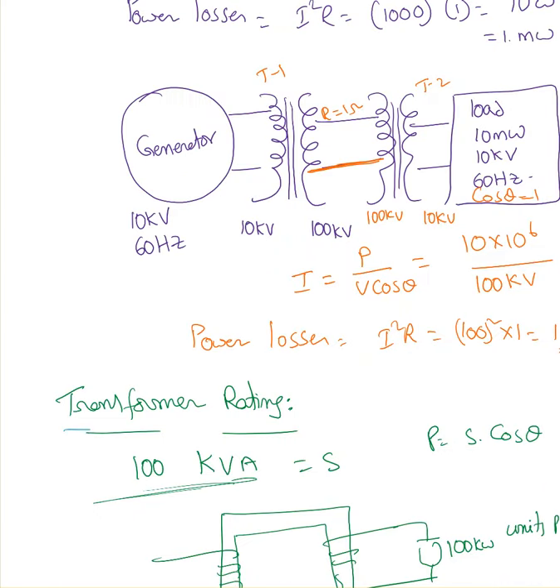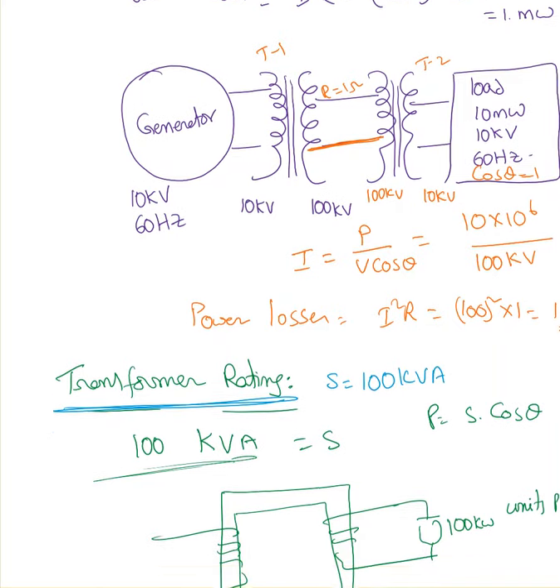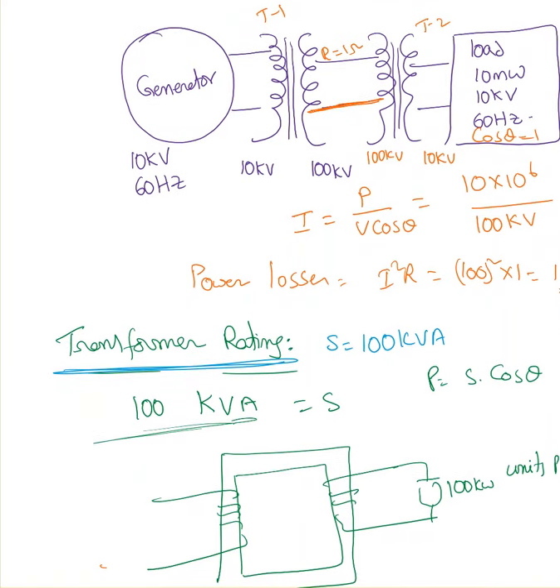The next topic is transformer rating. The transformer rating is always in kVA - 100 kVA, 200 kVA, 500 kVA, or 80 kVA, 20 kVA, something like that. Why is that? Because at the time of manufacturing, the manufacturer doesn't know what kind of load you are connecting.